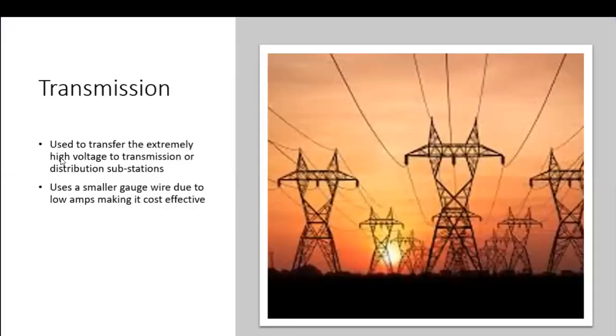Our transmission lines are used to transfer the extremely high voltage to transmission or distribution substations. They use a smaller gauge wire due to the low amps, making it cost effective. Well, we're transmitting at such a high voltage that our amperes are lower, and they're able to use a smaller conductor.